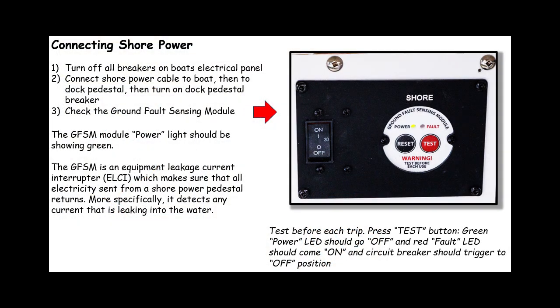The process for connecting to shore power begins by turning off all the breakers on the boat's electrical panel, so we don't have a large load suddenly come on when we turn on the power switch. Then we connect the shore power cable to the boat, go over to the dock pedestal and connect it there, and turn on the dock pedestal breaker. Coming back on board into the cockpit, we open the back seat hatch and check the ground fault sensing module, making sure the power light is green and no fault is indicated.